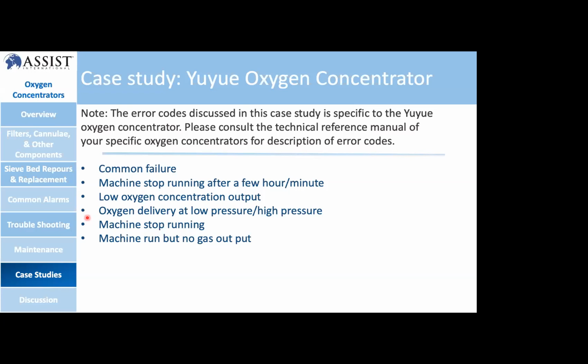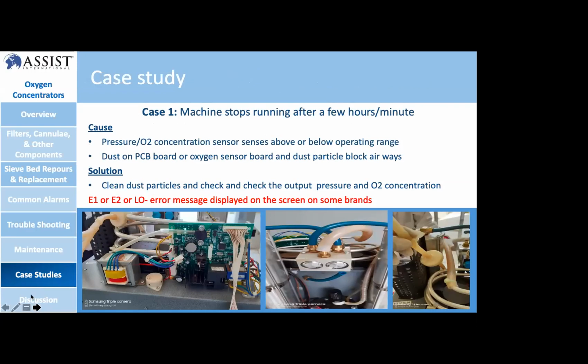The fourth one is the machine totally stops running. That means when we just plug in the machine or turn it on, it does not run at all. And the fifth common failure we face is the machine runs but there is no gas output. That means the machine is running, it seems to be working properly, but there is no gas at the output, no gas delivery to the patient. This is also another problem that we faced in our activity.